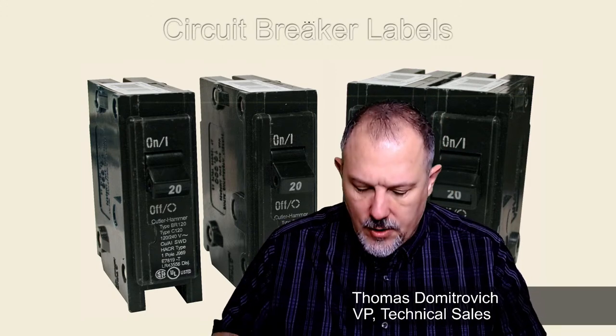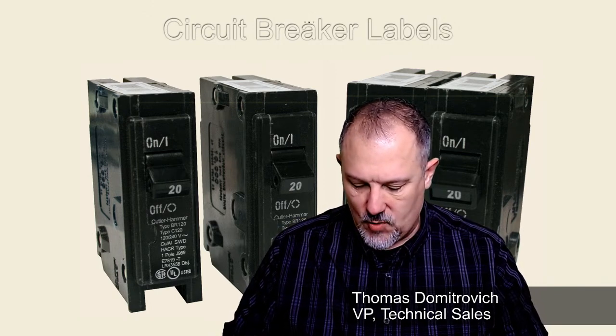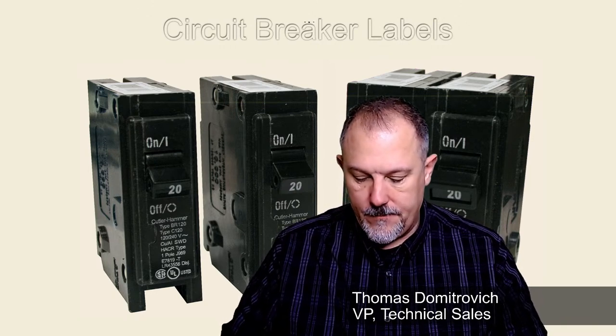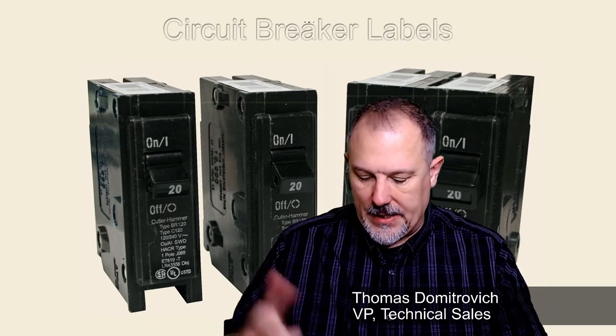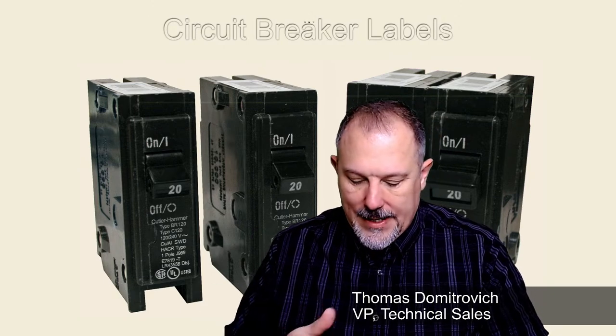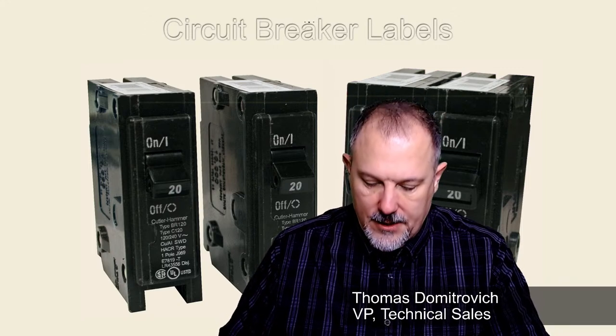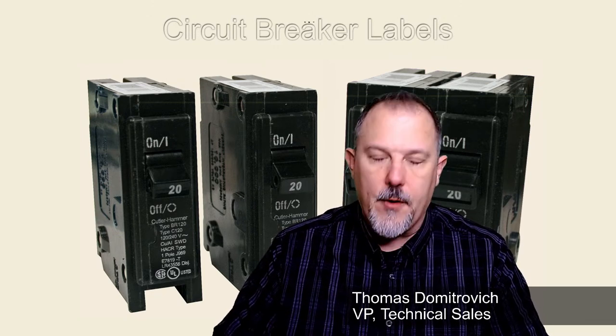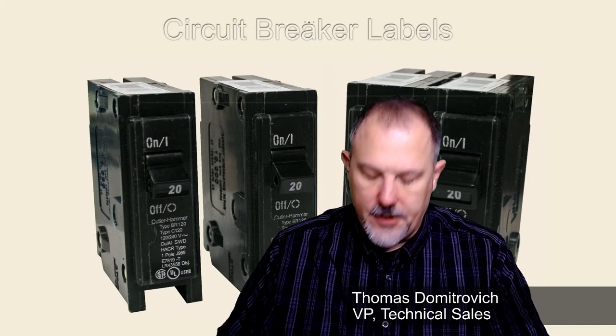Just looking, yeah. So I go to 310.16 and I'm trying to figure out what would be good here. Let's say, I don't know, I'm just picking a number. The difference between a 75 degree C and a 90 degree C column is what I'm looking for. I got 130 amps that I can put on a number one conductor. A 1 AWG, American wire gauge, 1 gauge wire, I can put 130 amps on that in the 75 degree column, but I can put 145 in the 90 degree C column.